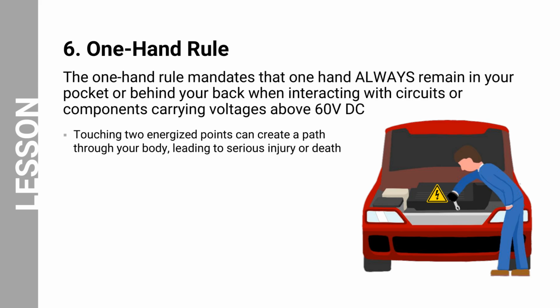The one-hand rule is a safety practice that mandates keeping one hand in your pocket or behind your back when working with circuits or components carrying voltages above a certain threshold, typically specified as 60 volts direct current, DC, or higher. It minimizes the risk of electrical shock by preventing current flow through the body, which can occur if both hands are in contact with conductive elements of different potentials. When you touch something energized with one hand and another conductive object, like a tool or another part of the circuit, with your other hand, you create a direct path for the current to flow through your body, potentially causing severe injury or even death, especially if the current passes through your heart.